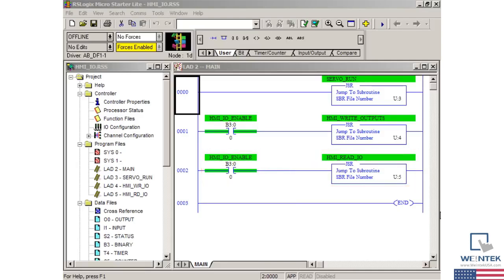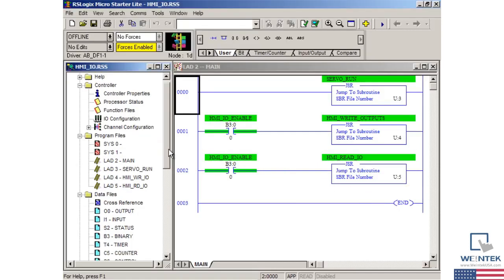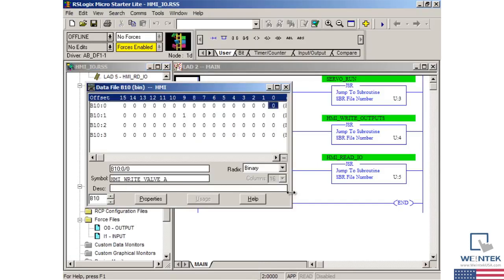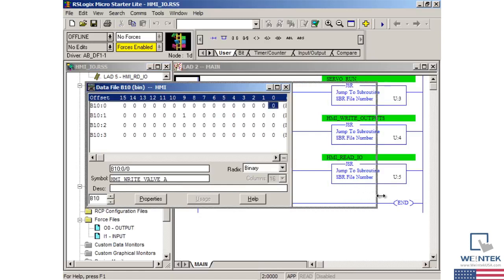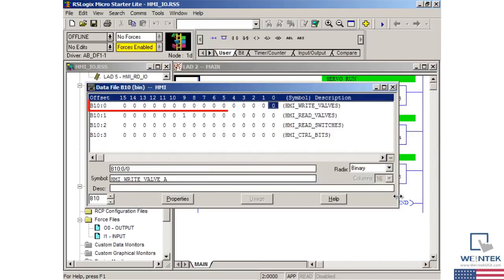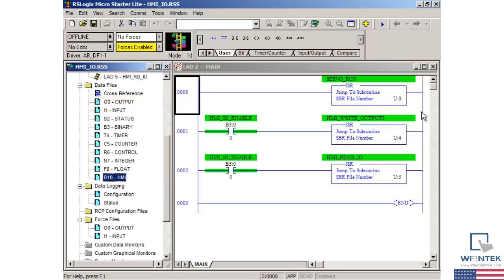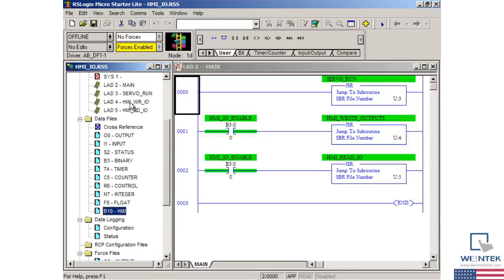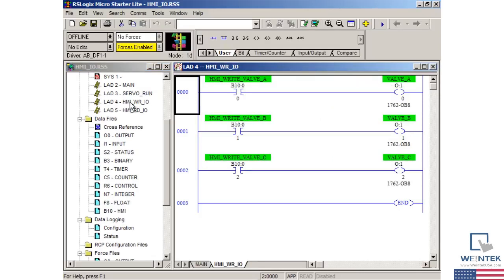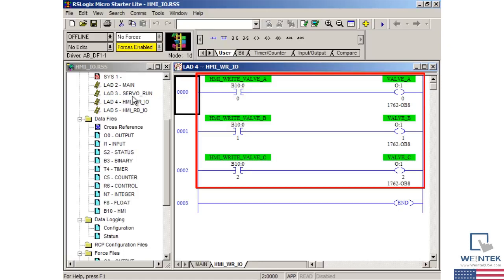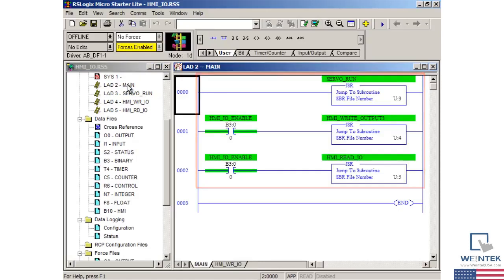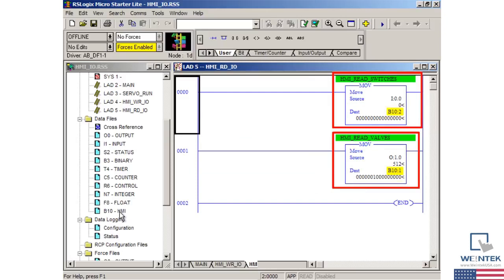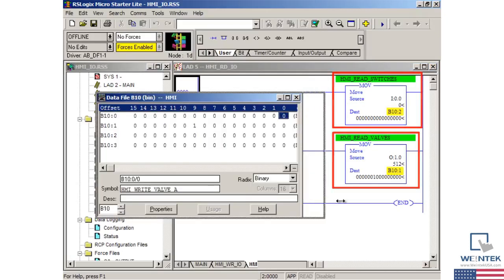Let's take a closer look at this simple implementation of an interface table in an RSLogix 500 application. I've got a table of bits here, which serves as my HMI interface table in this toy program. For example, the HMI can write to these bits to control PLC outputs. If the running PLC program has enabled HMI control, then a simple subroutine copies the bits from the HMI interface table to the outputs every scan. In this case, we have copied bit by bit because we like to be very explicit when allowing HMI control of outputs. In servicing the HMI reads of IO, we just move or copy entire words of input and output bits to the interface table for HMI access.